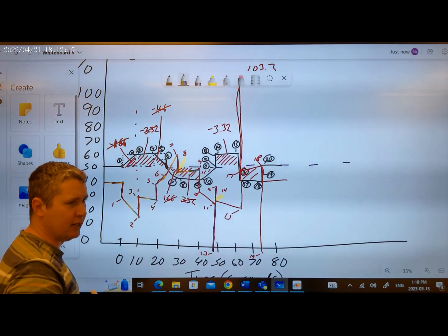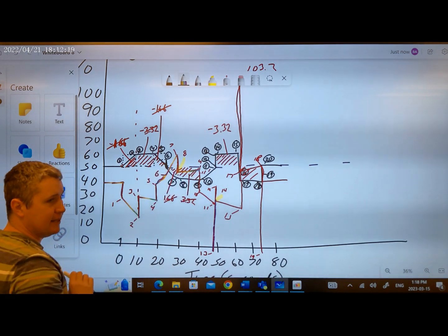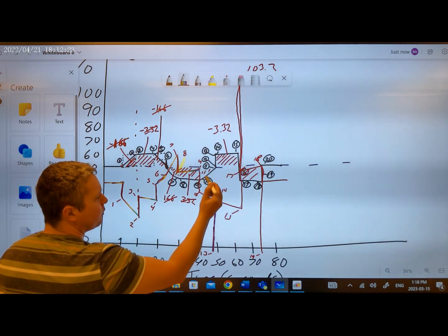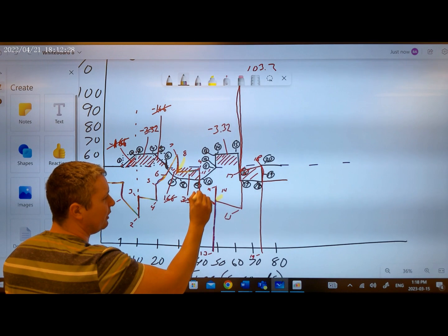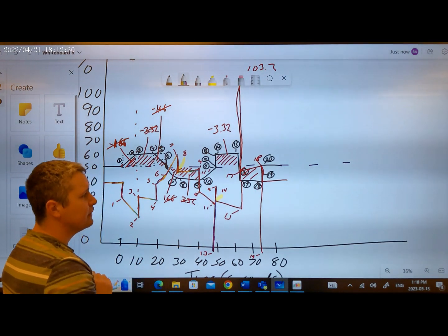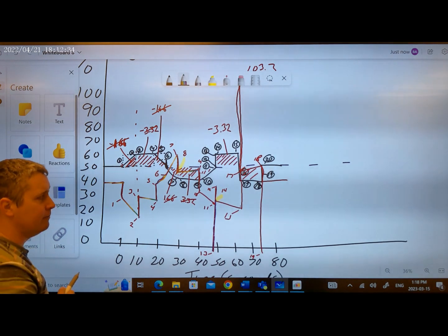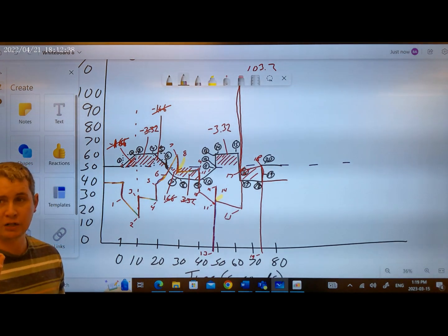That's what the integral is trying to do: over time, bring your process variable back to the set point. Then we get another ramp rate, causing our derivative to make our output drop. Our integral didn't have any time. Our proportional did not change. The only thing that changed is we then got a ramp rate.